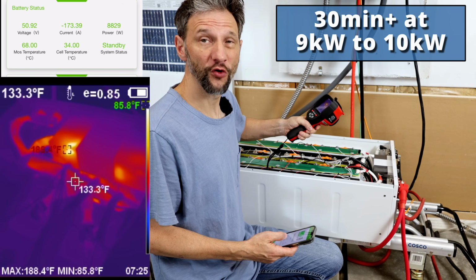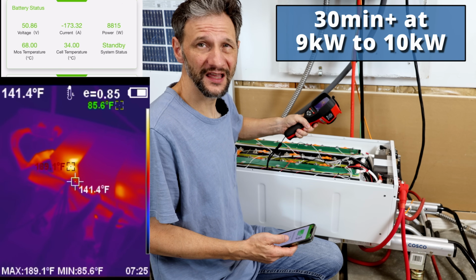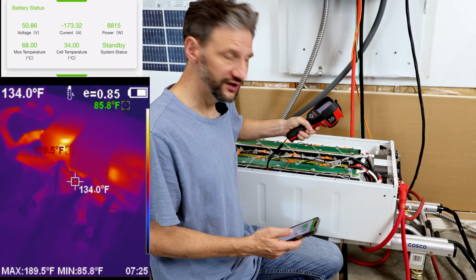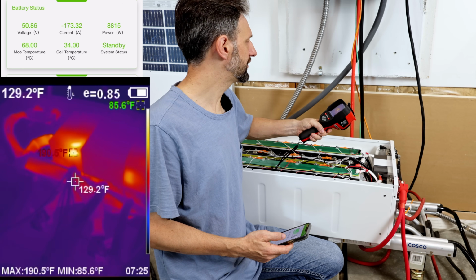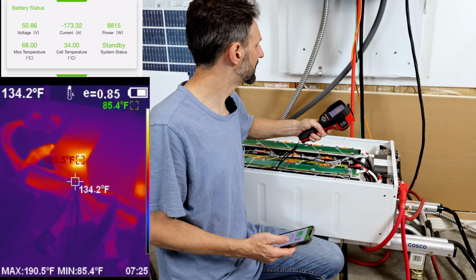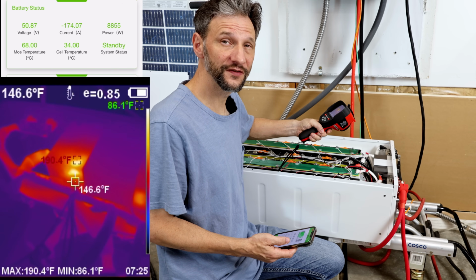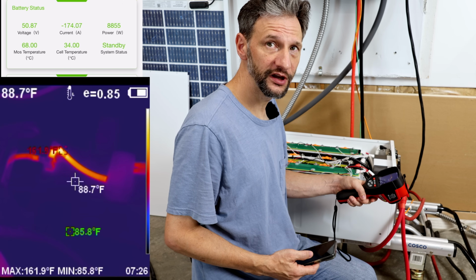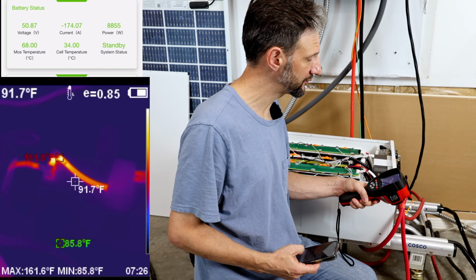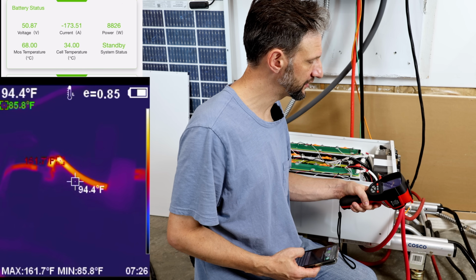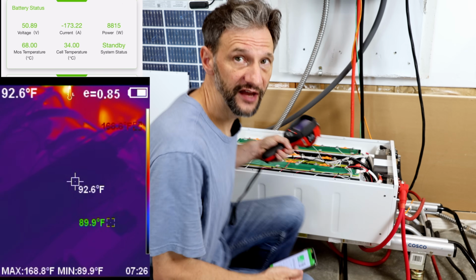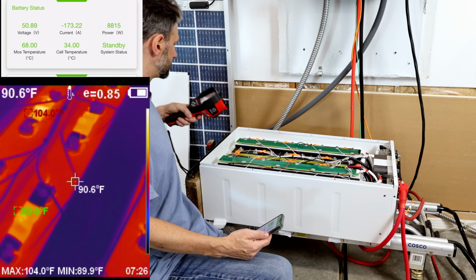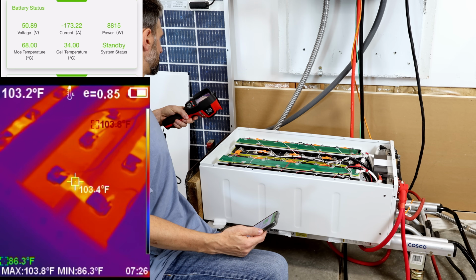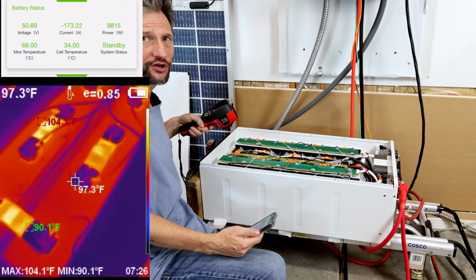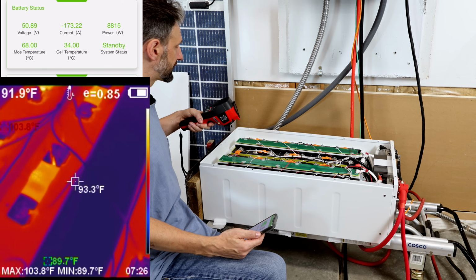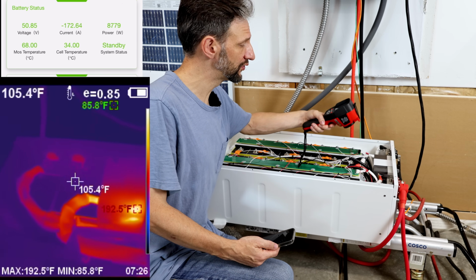All right, we've been running this thing for over 30 minutes now, between 9,000 and 10,000 watts, really close to its maximum. And you can see the breaker's starting to get pretty warm. It's 190 degrees Fahrenheit. The one cable carrying the most load there is maxed out. It seems it's saturated at 180 degrees or so. But everything else in the battery looks really good. I mean, it's just barely over room temperature. It's almost 90 degrees in my garage, so the terminals are nice and cool.